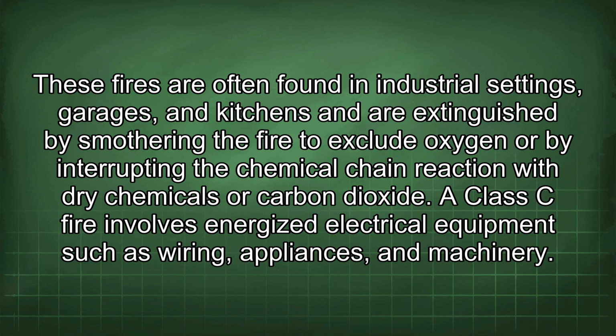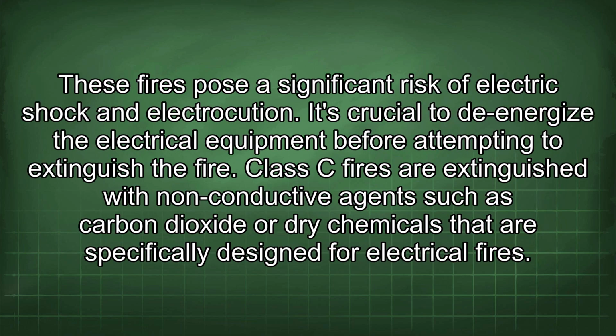A Class C fire involves energized electrical equipment such as wiring, appliances, and machinery. These fires pose a significant risk of electric shock and electrocution. It's crucial to de-energize the electrical equipment before attempting to extinguish the fire. Class C fires are extinguished with non-conductive agents such as carbon dioxide or dry chemicals that are specifically designed for electrical fires.